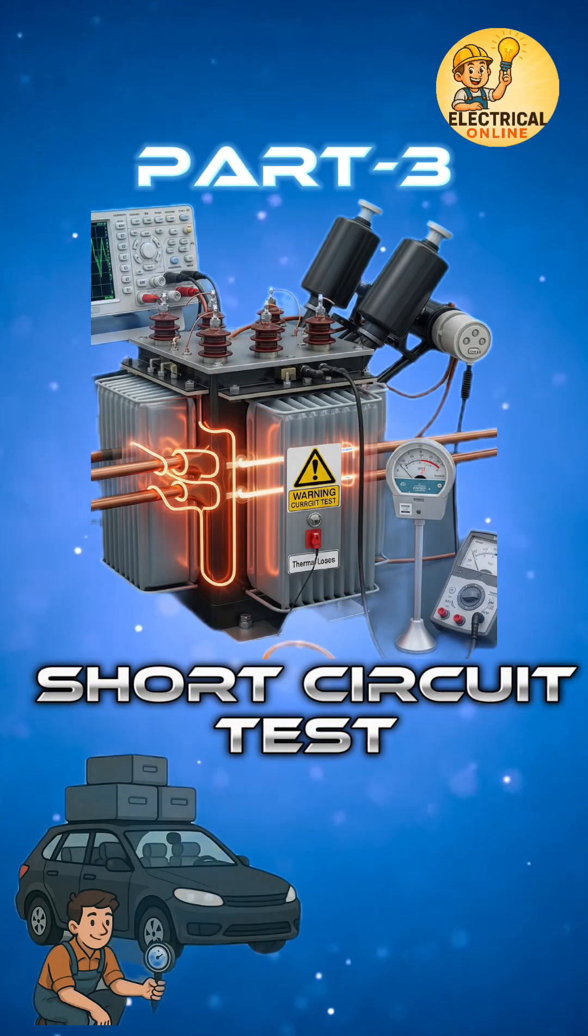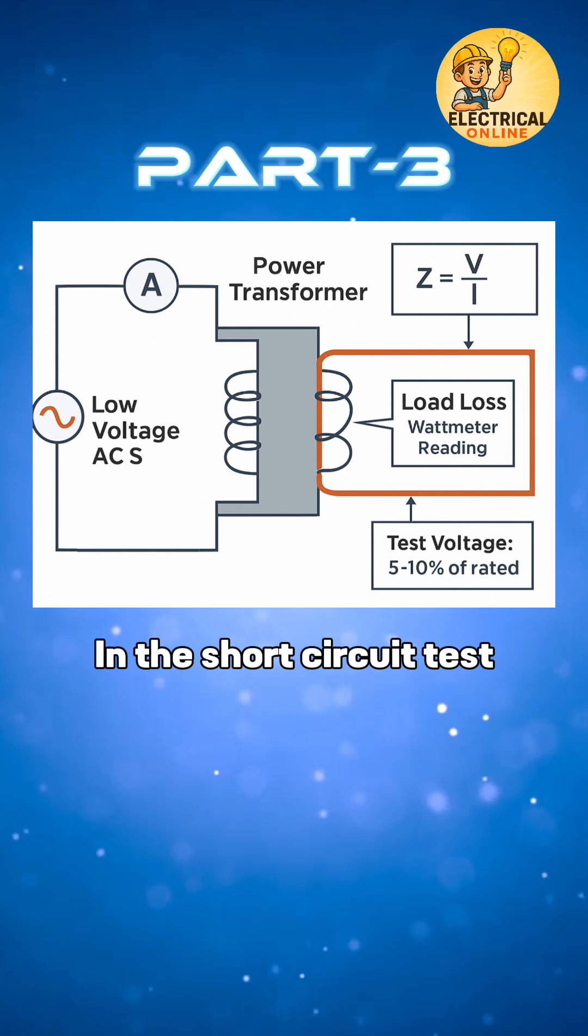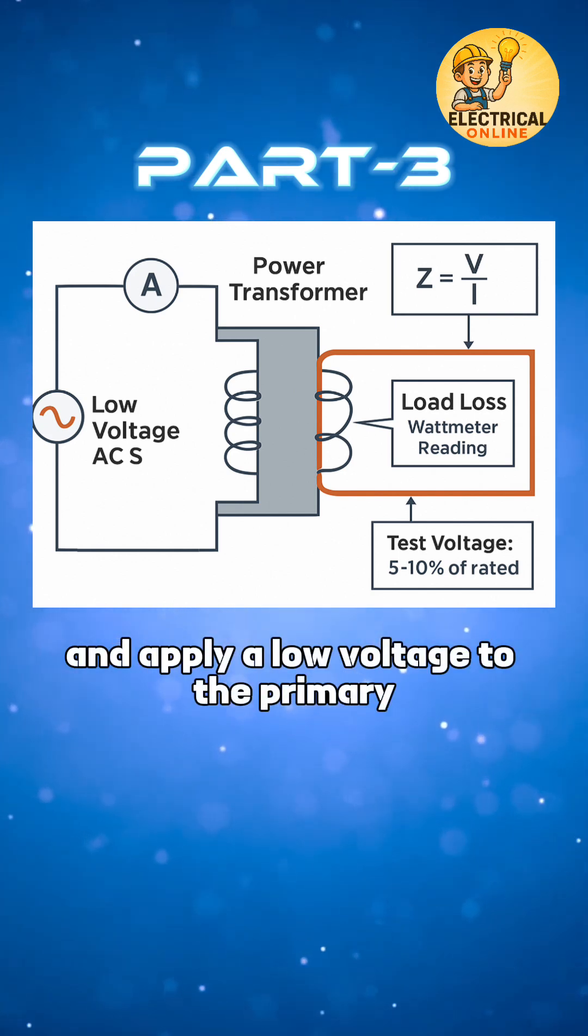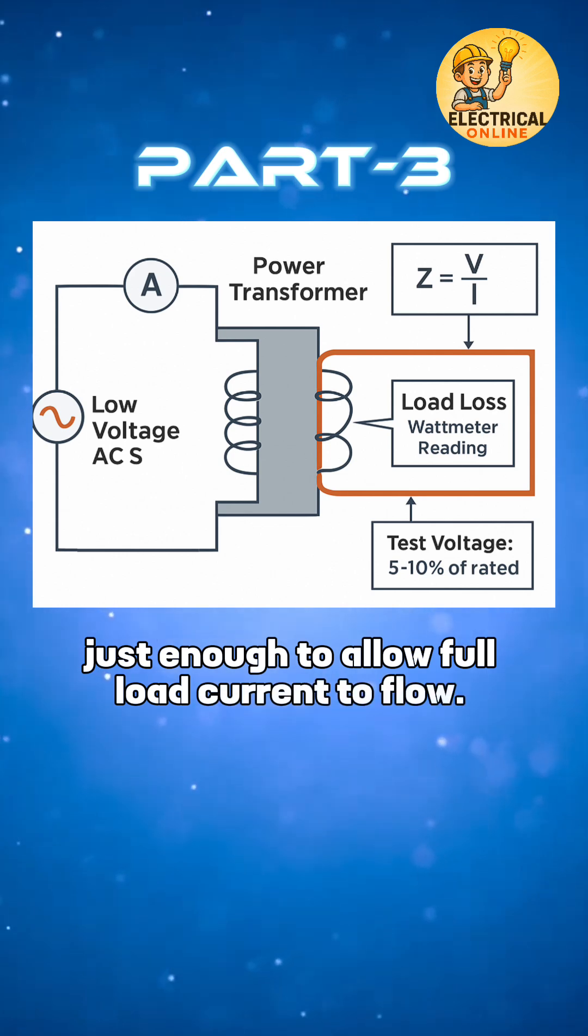In transformer test series, the third one is short circuit test. In the short circuit test, we intentionally short the secondary winding and apply a low voltage to the primary, just enough to allow full load current to flow.